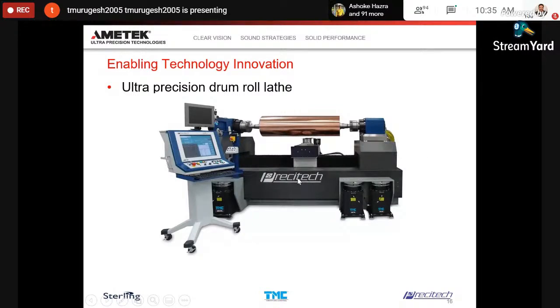So if you look here, it's a granite bed. I do not know if I have some time. I would also like to touch on vibration control. These machines are usually housed on a granite bed, under which there are isolators, which lift the whole granite bed, because we need to have very, very minimal vibrations on the floor. So this vibration control eliminates the floor vibration, making the top of the machine absolutely vibration free, which is very important.